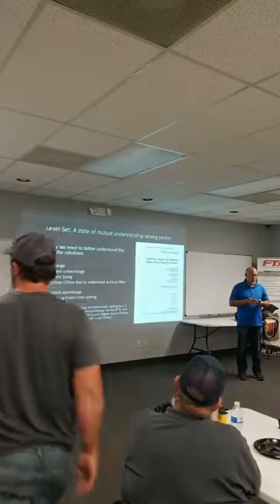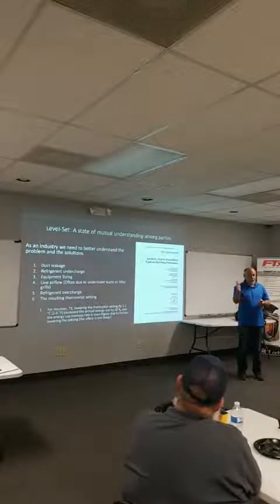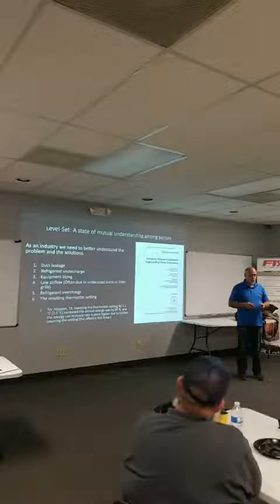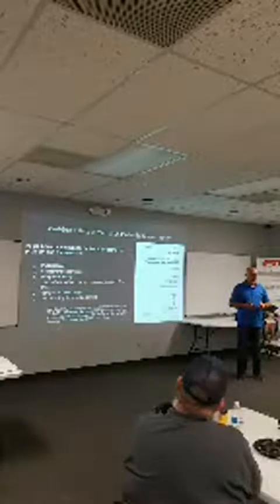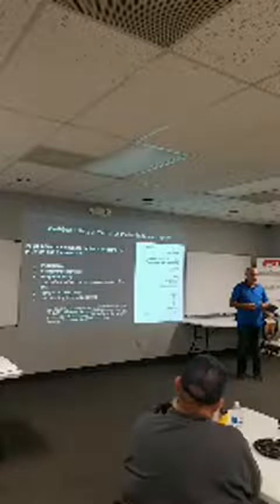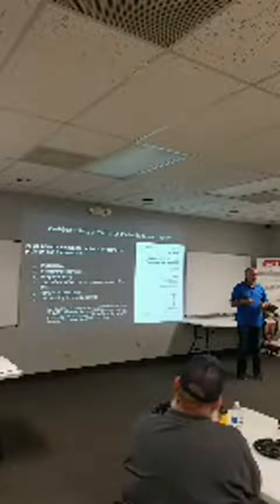But you're only at design conditions, right? Well, theoretically, but what if your air conditioner's got a dirty condenser? Now your balance point just shifted. Because if you can't reject heat outside, how does it get back into the evaporator coil? Through the refrigerant. What line does the heat that's not rejected by the condenser come back in on? The liquid line. Well, what temperature does the liquid line have to get down to at the metering device? 40 degrees, say. The saturation temperature of the evaporator coil, whatever it is, okay? Here's the thing.